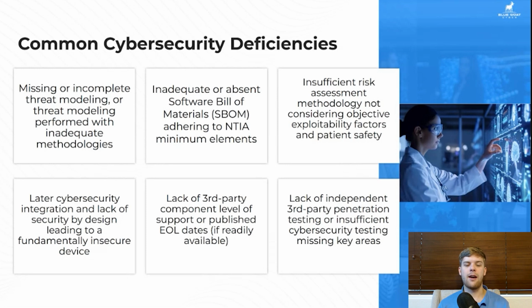Finally, another very common cybersecurity deficiency is lack of independent third-party penetration testing or insufficient cybersecurity testing. There's a very long list of different cybersecurity testing activities, and the penetration testing needs to be done by an independent third party, and you need to prove that independence. If this is done in-house, it will likely be rejected by the FDA. If we're missing any of these different types of cybersecurity testing, it will also likely be rejected by the FDA.